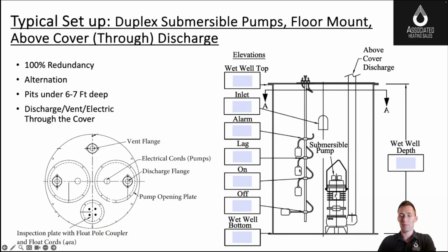Duplex pump systems have 4 position points for their controls. Typically they're floats. We'll talk about the options here. But the off float down here turns the pumps off. The next float is the lead, or the on float, turns the pump on. The next float is the lag, turns the second pump on. And the high water alarm is the next float. Our control panels are alternating. So each time a cycle happens, a different lead pump turns on. So they're alternating control panels.